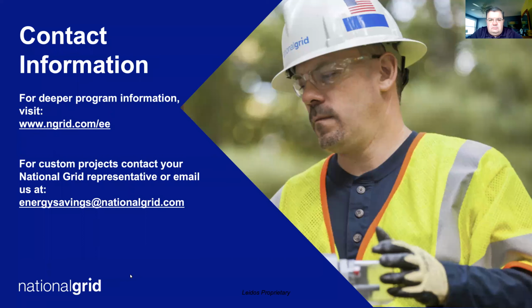Yeah, so I think there might be a typo on their part. It's supposed to be DCV, so demand control ventilation. For those that don't know, with demand control ventilation, you control your ventilation based on the demand. Demand is typically measured by CO2. As you have more people within a space that are exhaling, they're increasing the CO2 levels, and you're bringing in more outdoor air in response to that. Conversely, as the building or space becomes less occupied, you can reduce the amount of outdoor air accordingly.